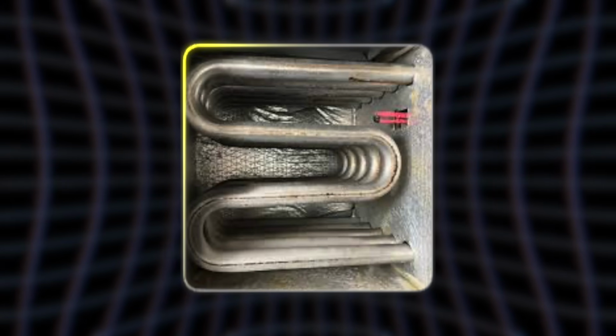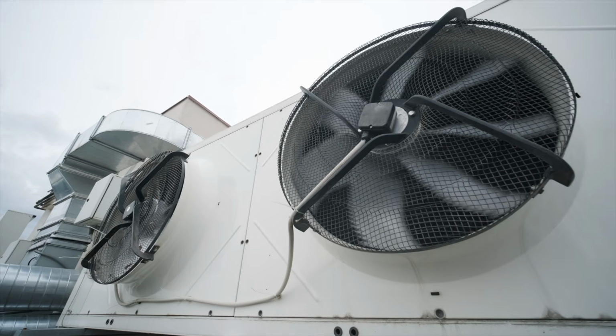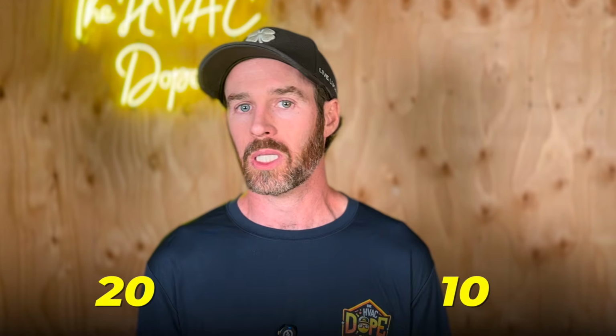Now, as far as replacing a system when you have a crack in the heat exchanger, the reason that I touched on earlier that it oftentimes makes sense to consider replacement when your heat exchanger is cracked is really just because you're throwing good money after bad at that point when you're looking at an old system with a cracked heat exchanger. And the reason is if you have a 15 or a 20 or a 25-year-old system and the heat exchanger is cracked, but you opt to replace the heat exchanger, every other component on that furnace, if your blower motor hasn't been replaced on a 15-year-old furnace, it's about to be replaced, because it's kind of at that age where from the 10 to 20 year mark is typically when blower motors go out.